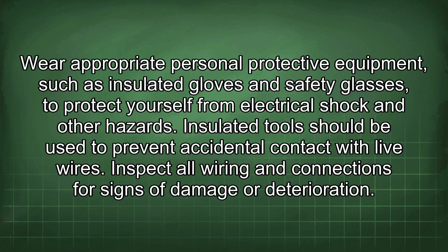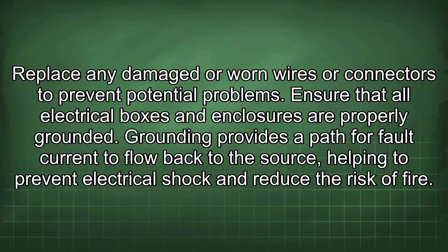Ensure that all electrical boxes and enclosures are properly grounded. Grounding provides a path for fault current to flow back to the source, helping to prevent electrical shock and reduce the risk of fire. Test ground connections regularly to ensure that they are functioning properly.